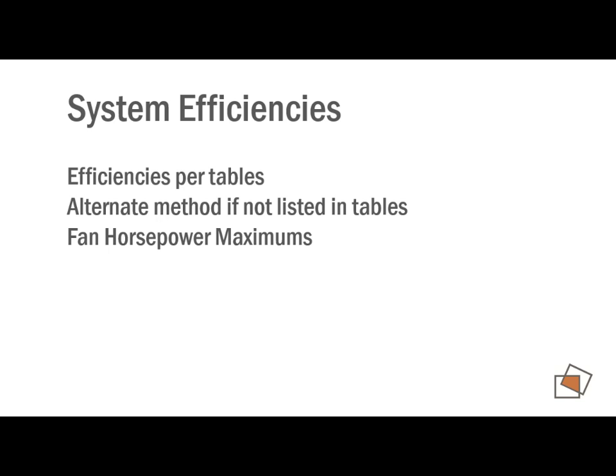The code also specifies fan horsepower maximums, so this is keeping us from putting a really big fan on and then a damper right in front of it to damper down the airflow. It's saying right size your system, right size your fan. Obviously you're gonna have adjustment, but they're giving you a cap on how much horsepower you can use for a certain CFM and pushing through a certain static pressure.